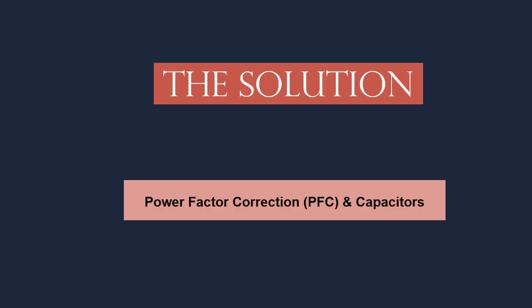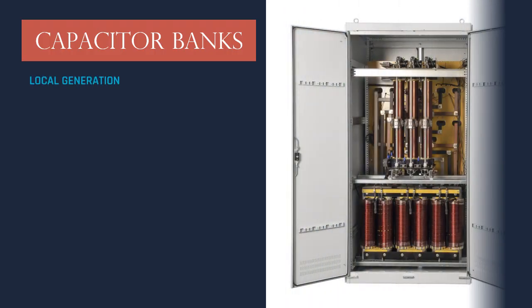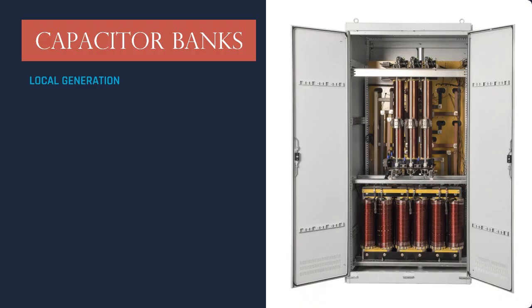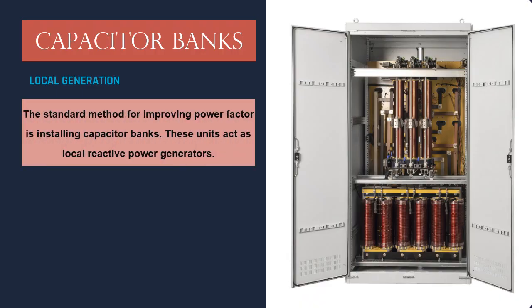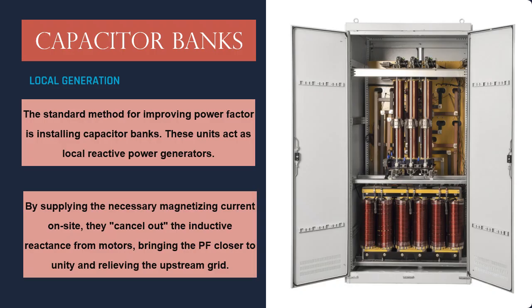Capacitor banks. The industry standard solution is the installation of capacitor banks. These units effectively act as local generators for reactive power. By supplying the necessary magnetizing current right next to the load, they cancel out the inductive draw from the motors. This relieves the upstream grid and brings your power factor back up towards unity.